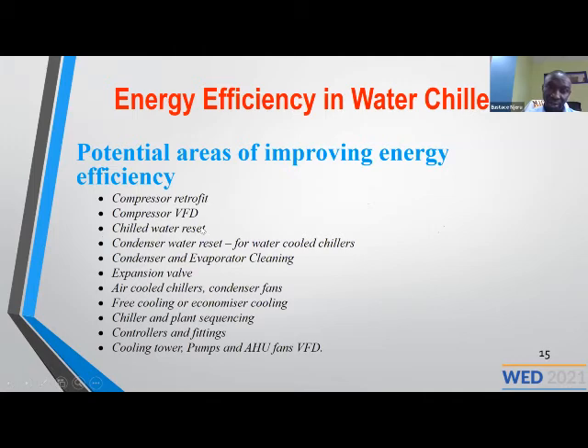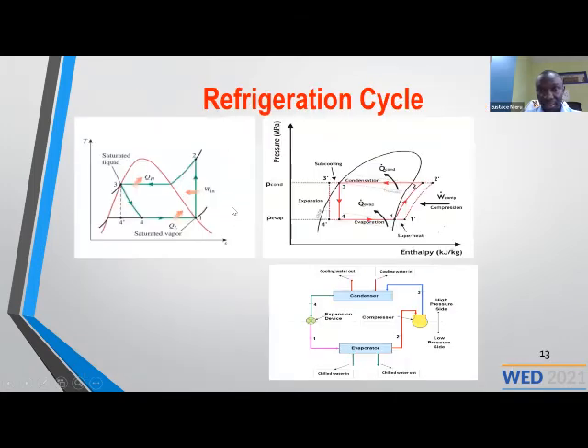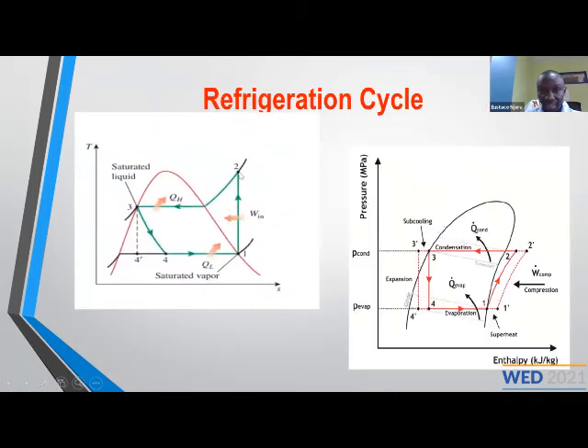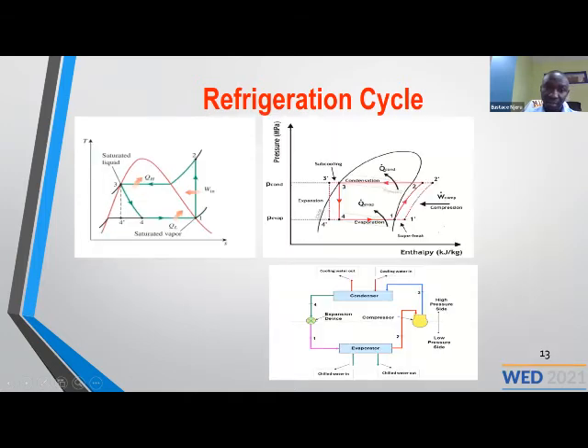You can do what we call chilled water reset on the evaporator side, where, depending on your demand for the cooling load, you don't require water at very low temperatures. Instead of chilling water to 6 degrees, you can use water at 8 or 10 degrees. And that will reduce the size of this line, which is proportional to the amount of work being done by the compressor, or the energy being consumed by the compressor.